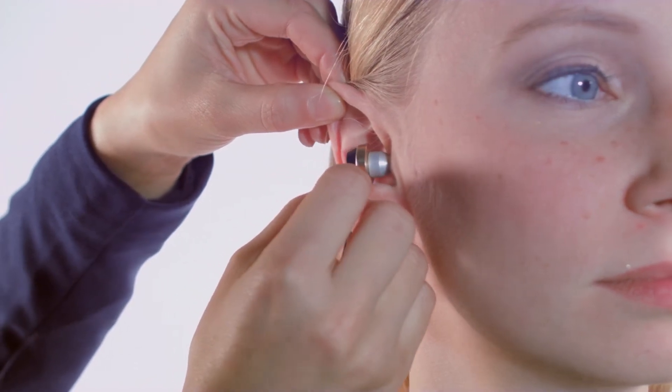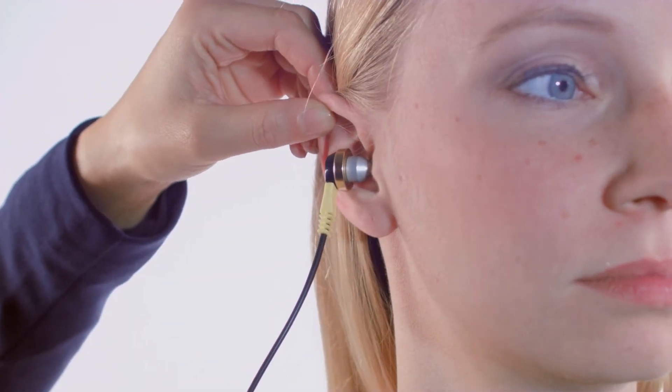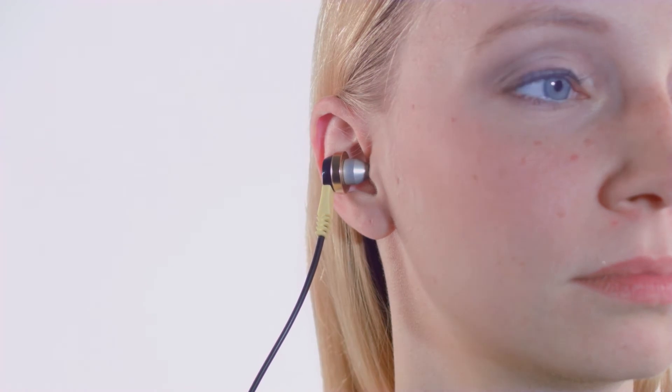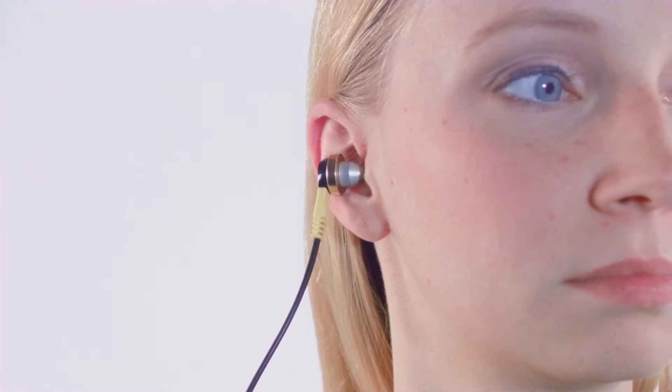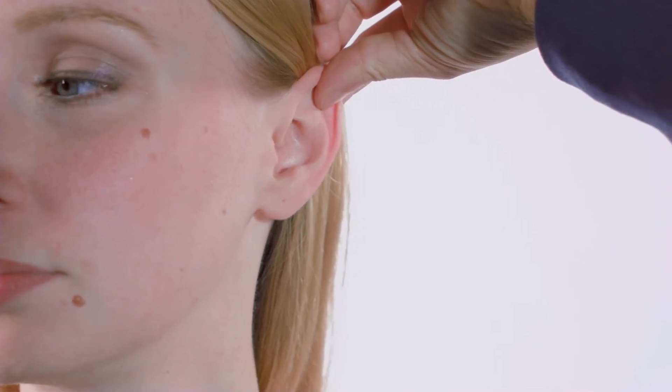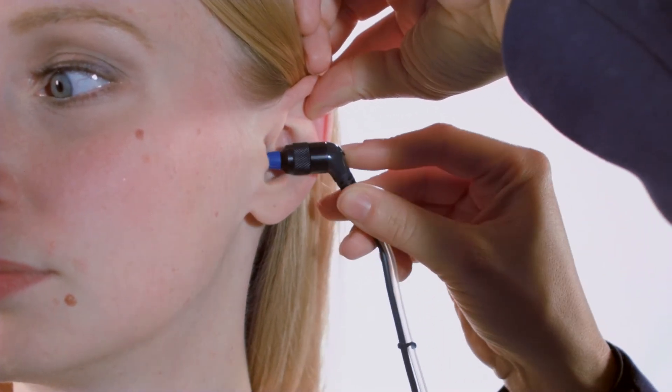Depending on the configuration, the probe also needs to be inserted in the test ear. The probe and phones should be placed far enough into the canal so that the probe will stay in place on its own without the tester holding it in place.